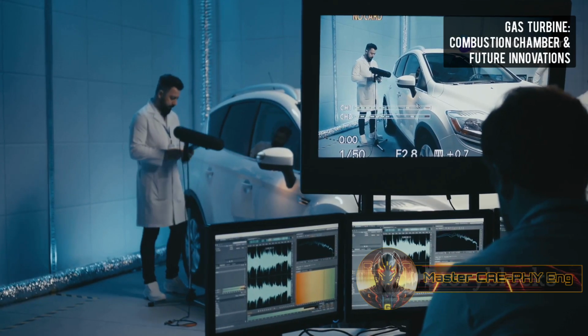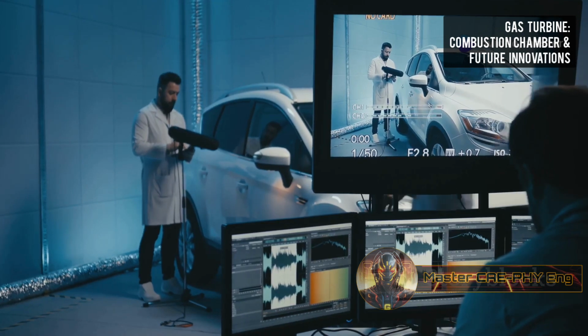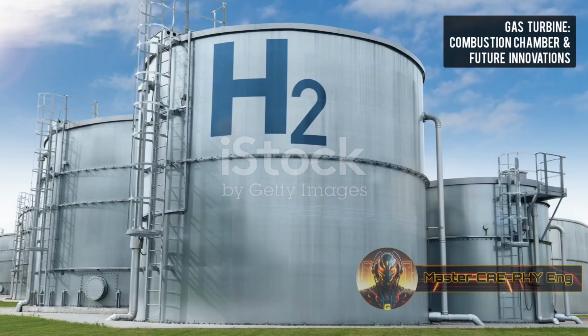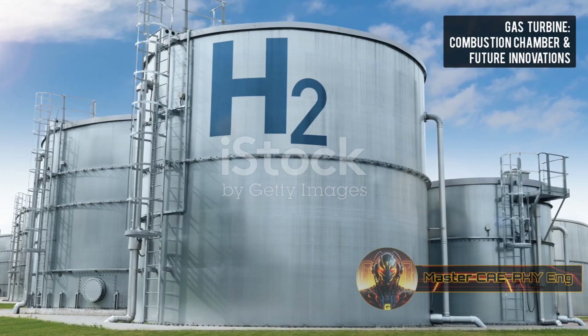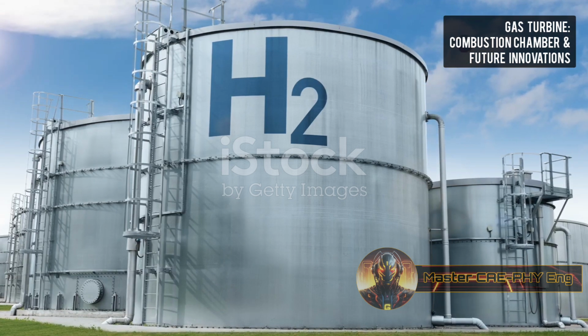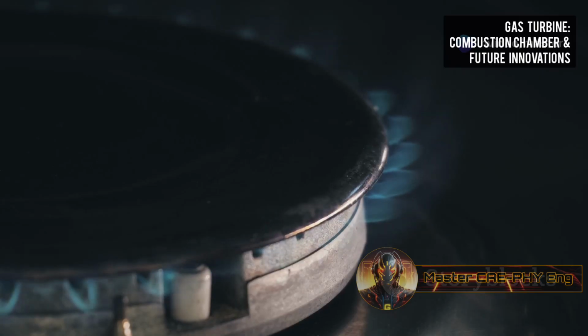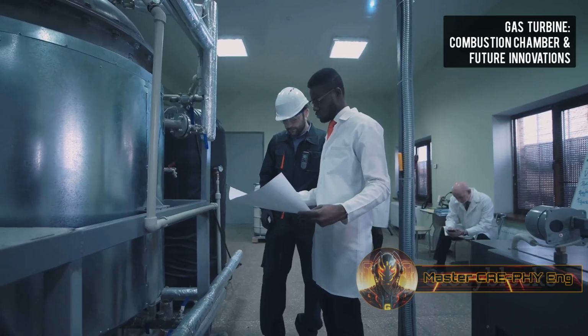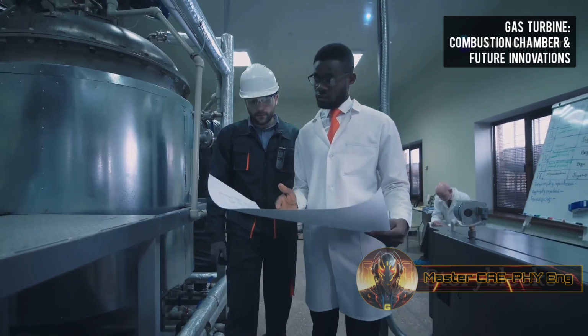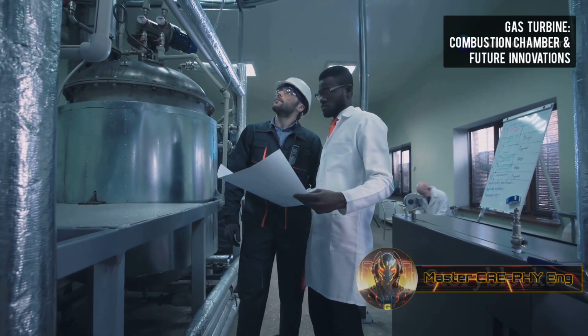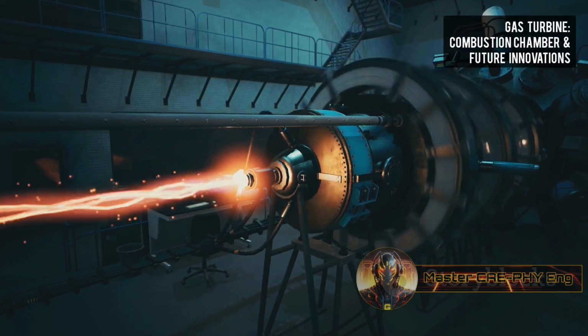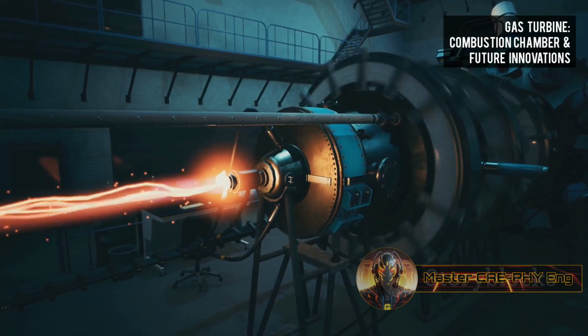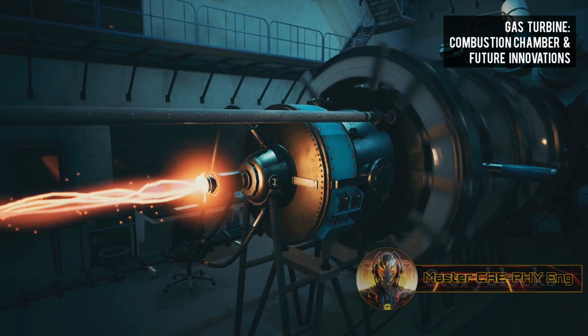The use of alternative and sustainable fuels is another major driver for combustor innovation. Hydrogen, as a carbon-free fuel, offers the potential for zero CO2 emissions. However, hydrogen combustion presents unique challenges, including a much higher flame speed, wider flammability limits, and a propensity for flashback. Combustors designed for hydrogen or hydrogen-rich fuel blends require new injector designs, flame stabilization techniques, and materials capable of withstanding different thermal loads and potentially hydrogen embrittlement.